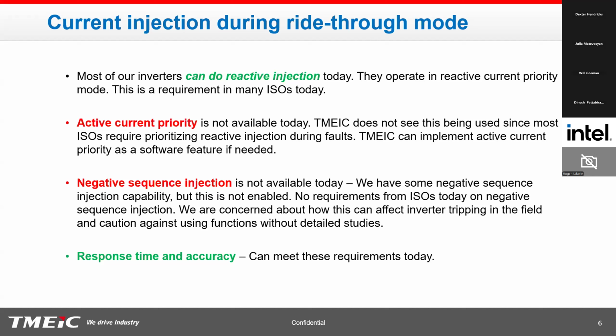Negative sequence injection, today we don't see any requirements from anybody requiring negative sequence current injection on the grid. At least to our best knowledge, most inverters today inject only positive sequence current during fault events. We do have certain negative sequence injection capability, but we do not enable it for our US market.